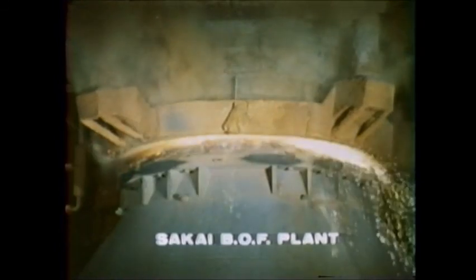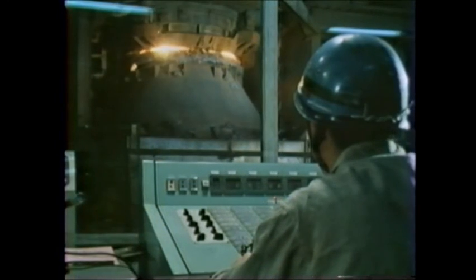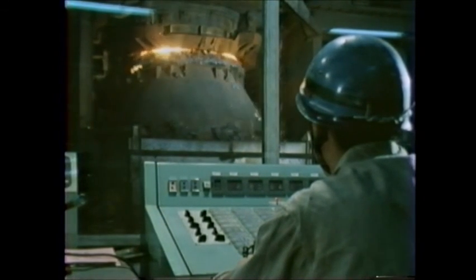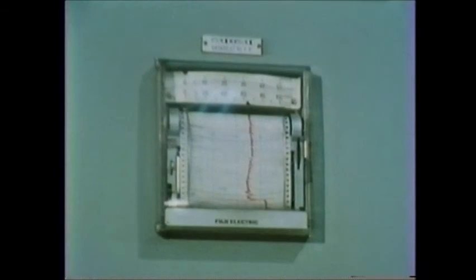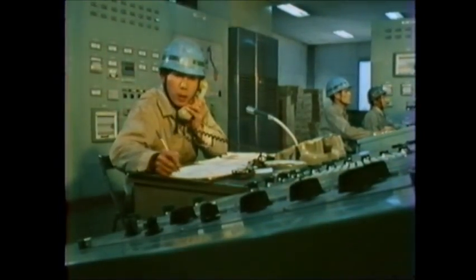During the intervening 7 years, many improvements were made in OG design and operation. One such innovation was the constant dry gas control. This method is based on the idea that the dry gas flow rate should be controlled constant, thus automatically causing a naturally controlled combustion sequence. This makes it unnecessary to modulate the set point of hood pressure. The operator merely adjusts the skirt position to obtain the desired ventilation effect without disturbing the degree of controlled combustion. This further simplifies the OG operation.